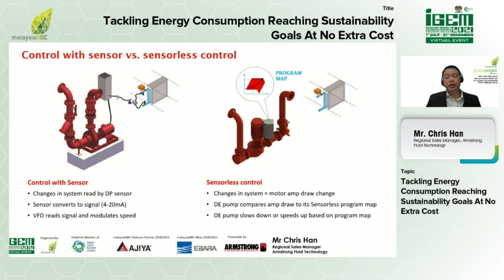Now, another interesting concept when it comes to parallel pumping. We know that in our HVAC environment, where partial loading is the norm, optimizing system performance isn't as simple as optimizing pump performance at a single duty point. The entire profile of the pump's efficiency at varying flows and speeds must be considered. In a parallel pumping environment, this makes selection and staging strategies even more complex. You will agree with me.